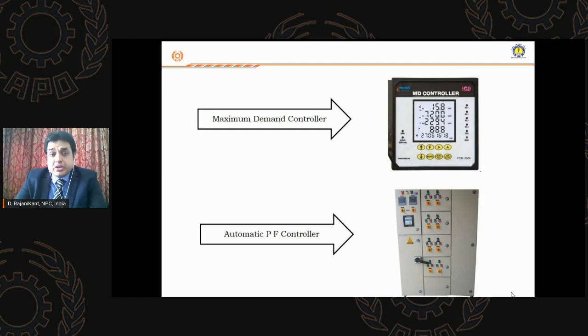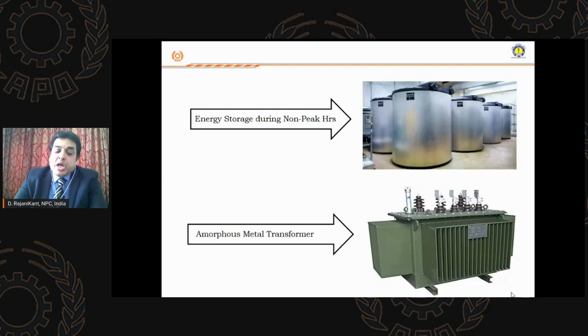you have automatic power factor controllers. Whenever you have a low power factor, these controllers will automatically add some amount of capacitors. When the capacitors are added, it compensates the power factor and always maintains it well above 0.95. To be precise, it is better to maintain it near unity, so that you won't have much penalty levied on your billing. If any SME starts analyzing their electricity bill thoroughly, or any technical consultant they hire does, from the electrical billing itself they will be in a position to understand the various penalties or various sections that they need to be very cautious about.